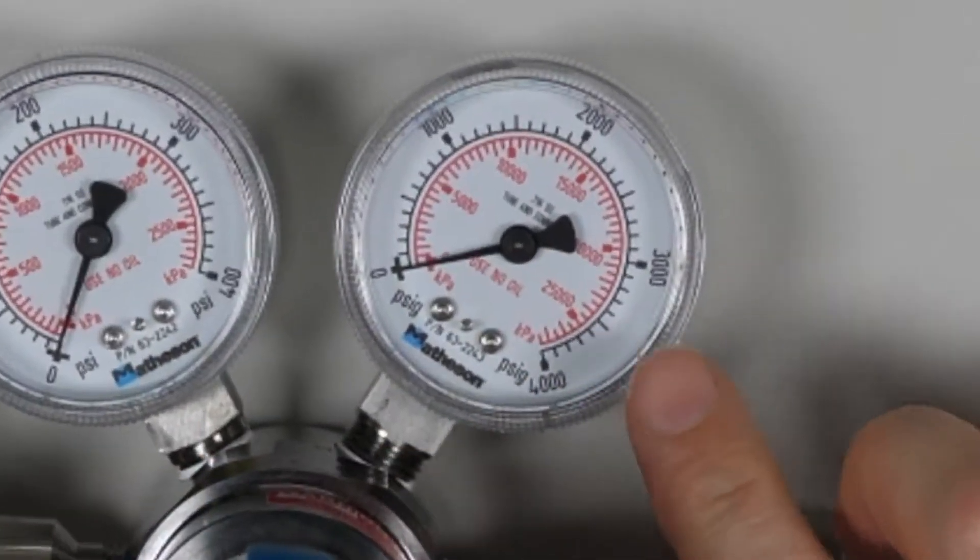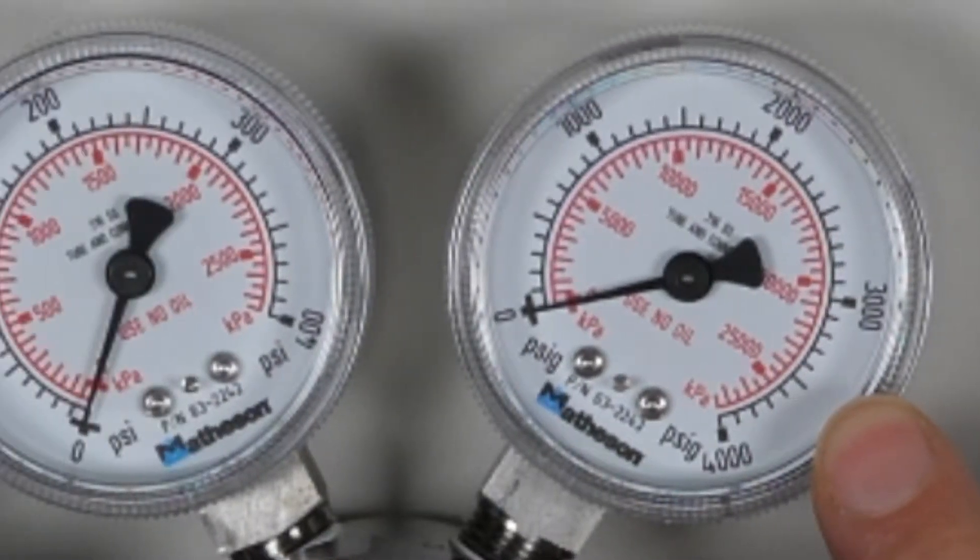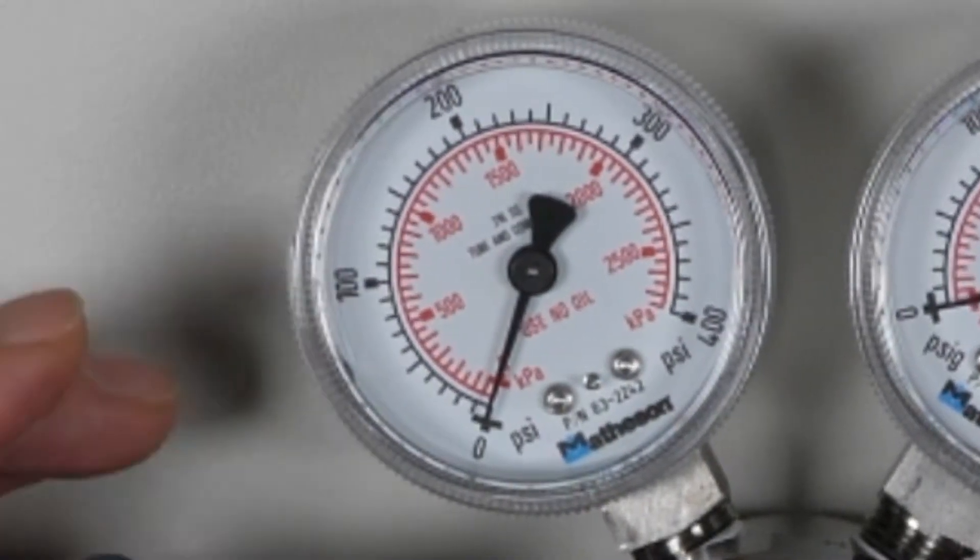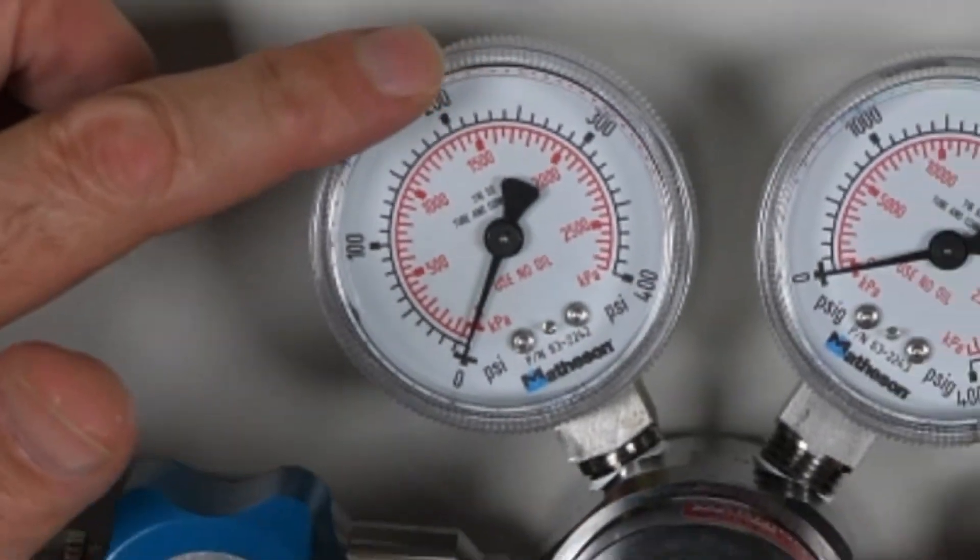Cylinder gauges are normally 3,000 or 4,000 psi. The maximum delivery pressure is typically in the middle range of the delivery pressure gauge.